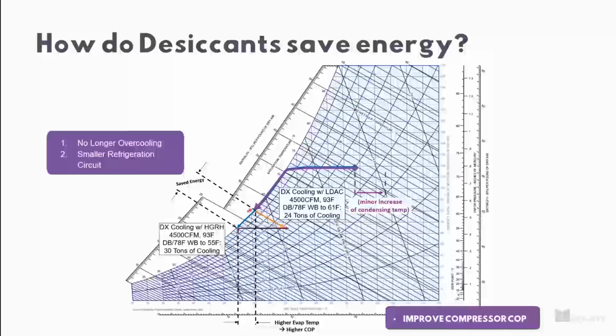And sorry, last thing here, just from an example perspective, in this particular case, with a hot gas reheat style system, it would take about 30 tons of cooling to bring you from 4,500 CFM down to 55 degrees dew point, or dry bulb, wet bulb dew point. With our system, only using about 24 tons of cooling to bring you to that 61 degrees off coil, and then leveraging liquid desiccant to do the rest of the effect, dehumidifying.